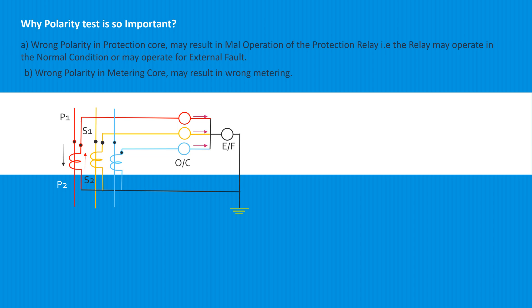In bus or transformer differential circuits, or overcurrent or earth fault circuits, the sum of currents should be zero. Any CT with reversed polarity would result in a non-zero current, which could result in circuit breakers opening.